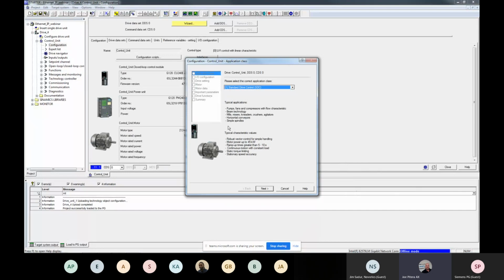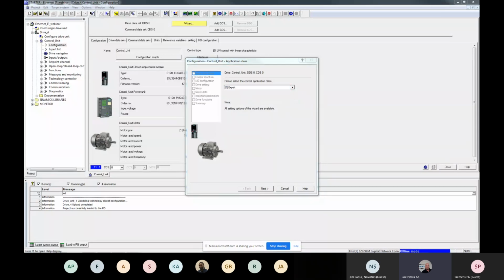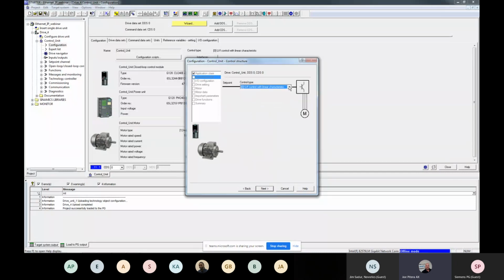The standard drive control will default the control method to use volts per hertz, whereas the dynamic drive control will use a sensorless speed control, open loop vector control. For this case, we're going to try and use maybe expert. So in this case, we now have a choice of how we want to set up the drive system here. We will try and do this one speed control encoderless or sensorless vector mode.